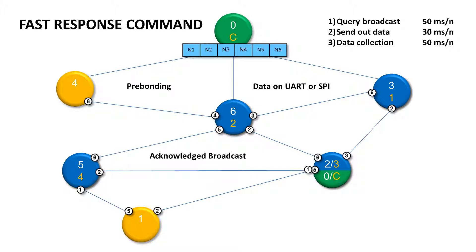The third predefined FRC is the acknowledge broadcast. This means that when you send this predefined FRC, you get a feedback from each node if the DPA request was performed or not. So for example, when you send an acknowledge broadcast command to switch on all lights, you'll get a feedback showing which light was and which one wasn't successfully switched on. This helps you to have your broadcast commands fully under control.